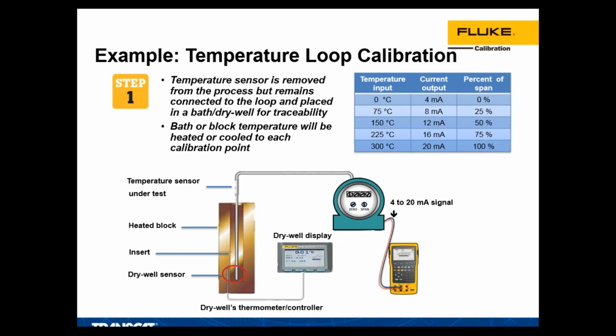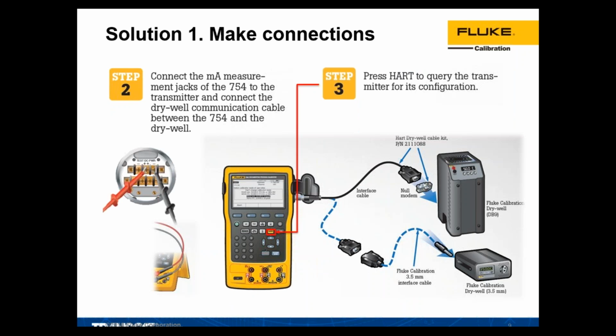How does the dry block know what the temperature is? If you look down in the bottom of that red circle, there is a control sensor down there. It's a little RTD that's in the block that measures the temperature right at the bottom of the dry well. And the display on the dry block is what's also recorded by the 754 through the communication. How does it communicate? Well, it looks like this.